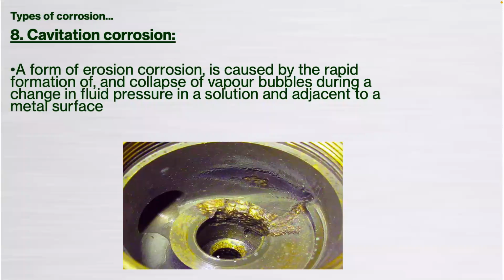If you go into a plant room and you hear a pump, one, it sounds very high pitched. It's running well above its curve, and it's struggling to draw, therefore, the right amount of water it needs to satisfy the pump curve. We can start seeing a pressure drop near or just upstream from the pump suction impeller, and we get these vapor bubbles occurring, and then you see sort of like a vortex of bubbles occurring right near the impeller, and it literally sounds like a bag of nails has been thrown in behind that pump almost. It could even be your strainers. You may have a blocked strainer, a dirty strainer at the pump. It's almost like closing back on the valve that serves that pump.